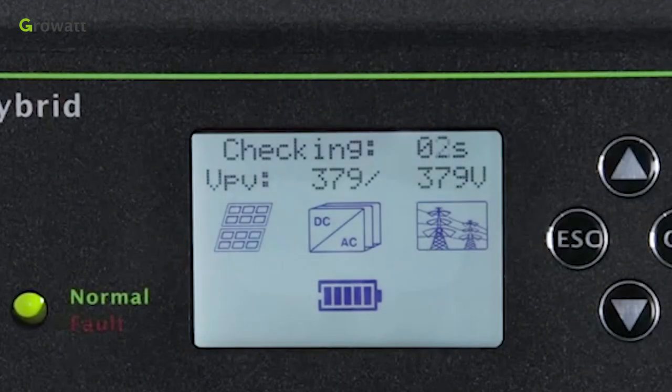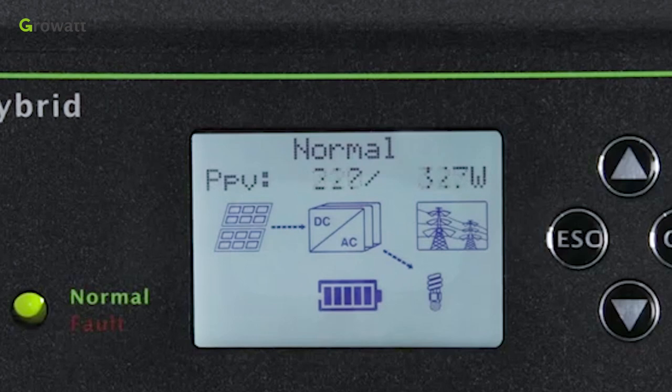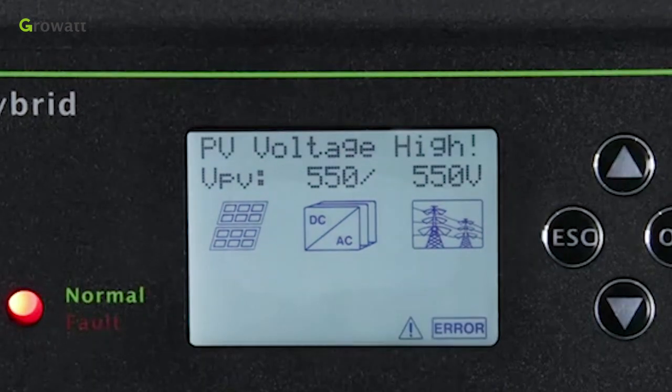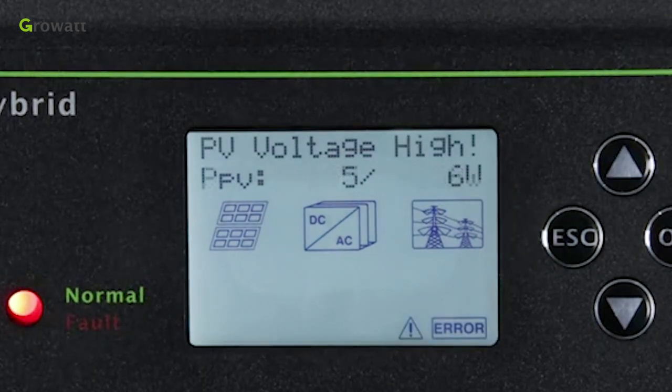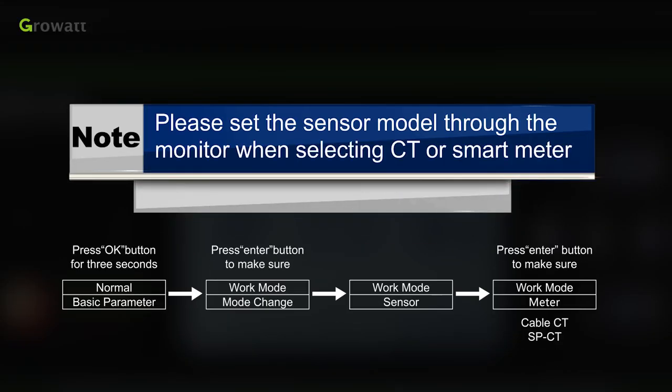After the system was powered on, if PV, grid and battery are available, the system will work on normal mode. When the SPH is on the normal mode, the screen shows normal and LED is green. If SPH didn't enter normal mode successfully, especially the LED is red, please contact Growatt Service Engineer for help. Note, please set the sensor model through the HMI when selecting CT or smart meter.